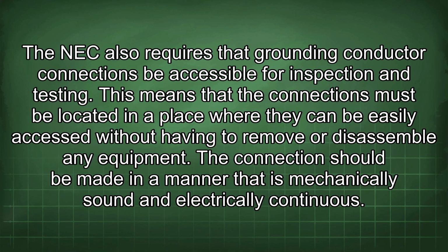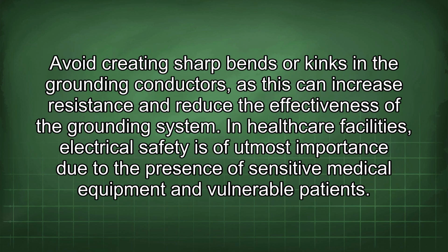The NEC also requires that grounding conductor connections be accessible for inspection and testing. This means that the connections must be located in a place where they can be easily accessed without having to remove or disassemble any equipment. The connection should be made in a manner that is mechanically sound and electrically continuous. Avoid creating sharp bends or kinks in the grounding conductors, as this can increase resistance and reduce the effectiveness of the grounding system.